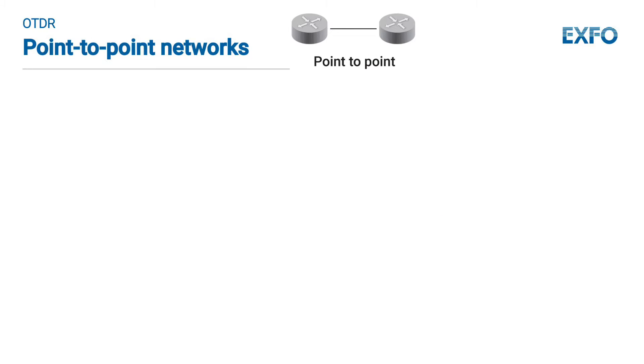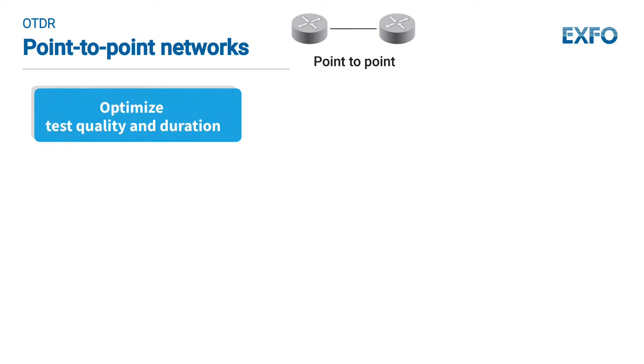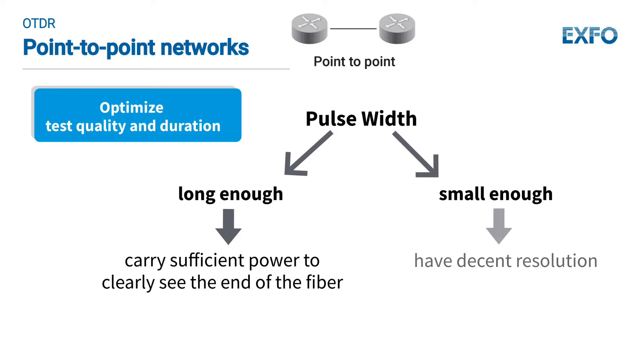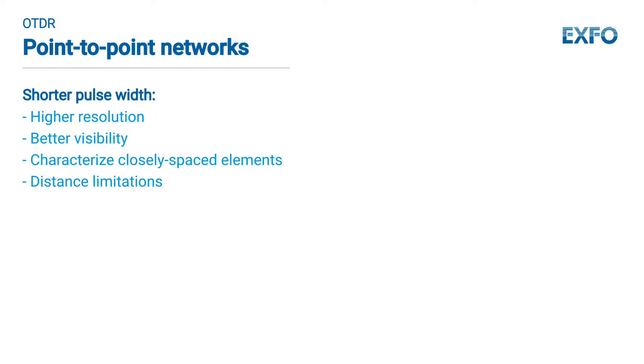For point-to-point networks, to optimize test quality and duration, the pulse width needs to be long enough to carry sufficient power to clearly see the end of the fiber, yet small enough to have decent resolution. A shorter pulse width is used to get a higher resolution, better visibility inside the link and to characterize closely spaced elements, but it has distance limitations.